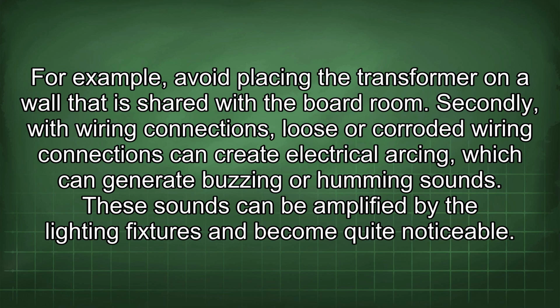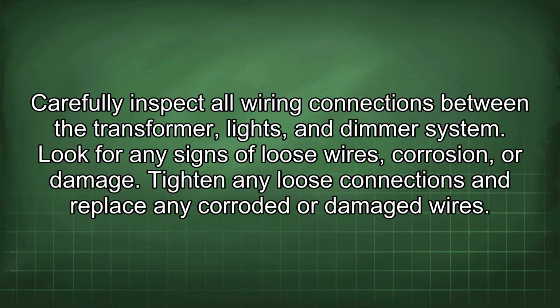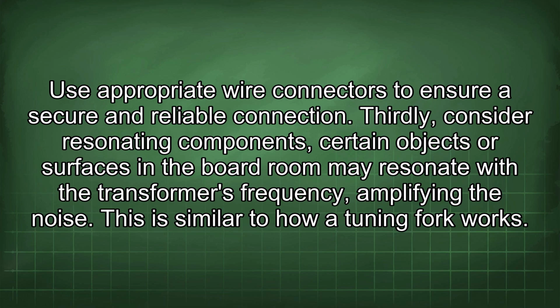Secondly, with wiring connections, loose or corroded wiring connections can create electrical arcing, which can generate buzzing or humming sounds. These sounds can be amplified by the lighting fixtures and become quite noticeable. Carefully inspect all wiring connections between the transformer, lights, and dimmer system. Look for any signs of loose wires, corrosion, or damage. Tighten any loose connections and replace any corroded or damaged wires. Use appropriate wire connectors to ensure a secure and reliable connection.